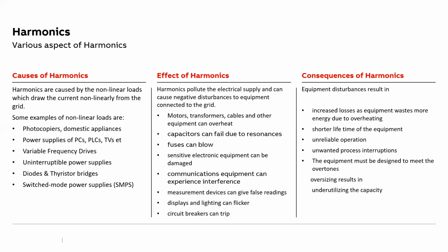So if we can ensure that the harmonics will be within the restricted levels. Now IEEE 519, the standard which governs harmonics, calls for a most stringent requirement of 5%. So if we are sure that the harmonics would be 5%, and if we know about the mitigation techniques, and we have taken proper care at the designing stage itself, we can eliminate all this oversizing and underutilization problem. We can reduce the cost of the transformer, the switchgear, the cables, and all the equipment. But this has to be planned properly during the designing stage itself.